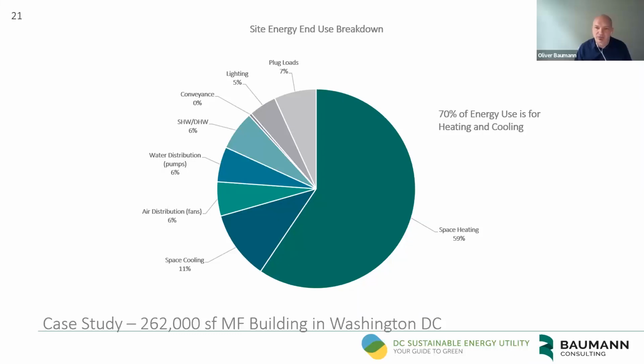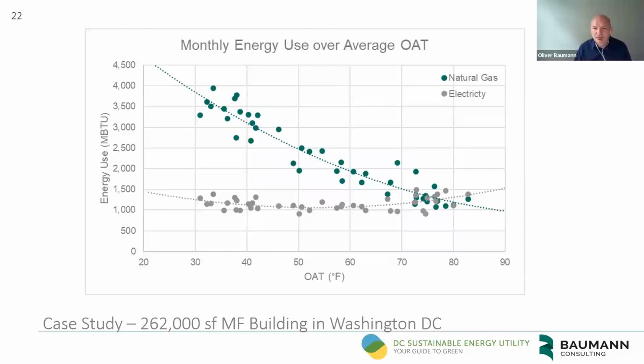Another step of the energy analysis, next slide please, is since we have monthly data, what we typically do is we sort the data and plot it over the monthly average outdoor air temperature. That's what we've done here. In that case, we use 3 years of data. We had utility bills and utility data for the last 3 years. I would say the more data you have, the better it is, because it gives you a better picture of the history of your building.